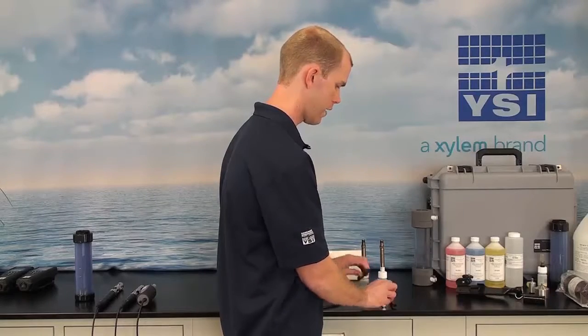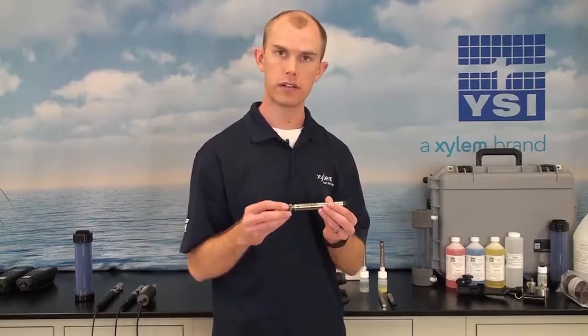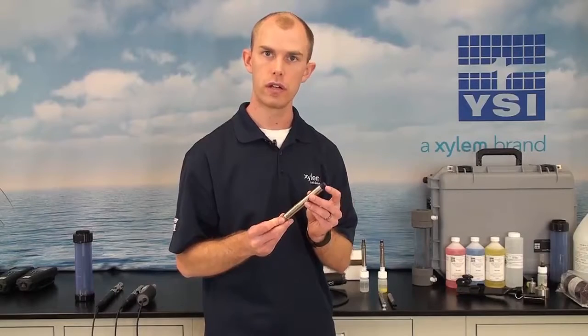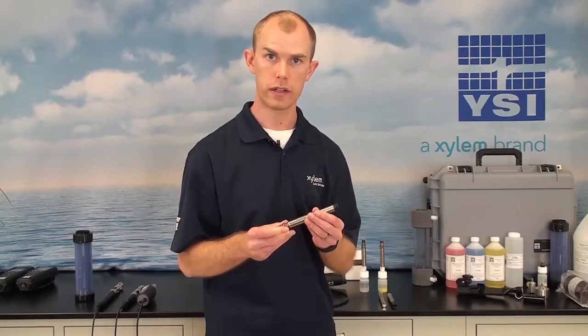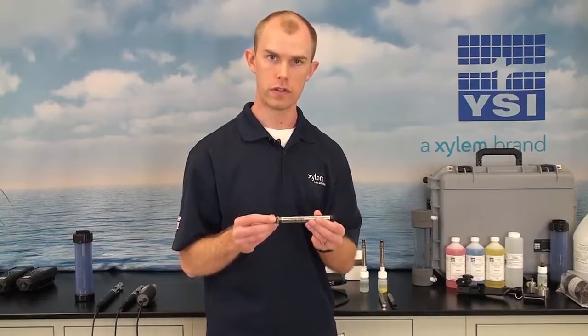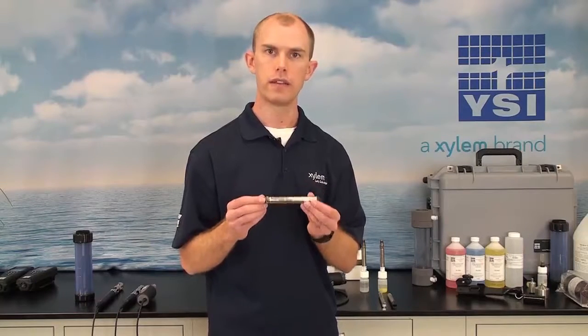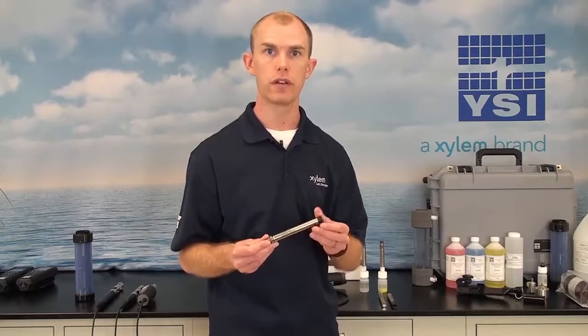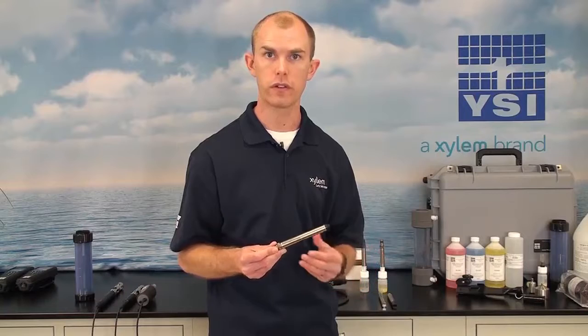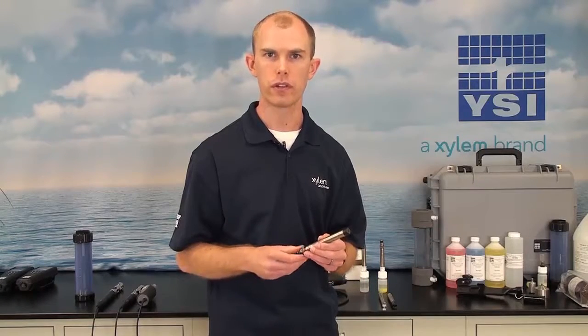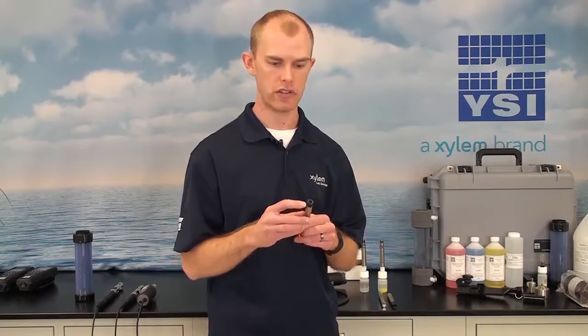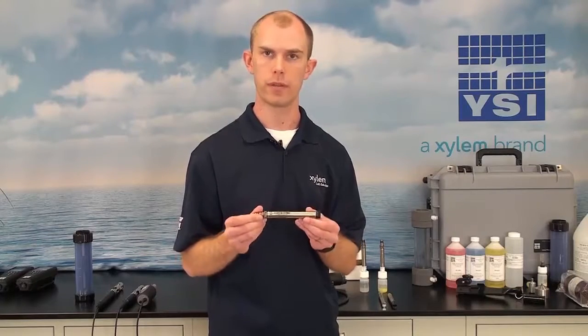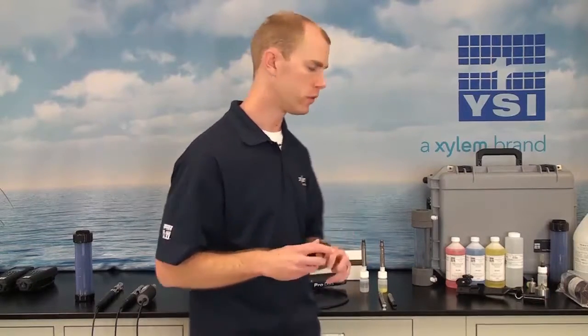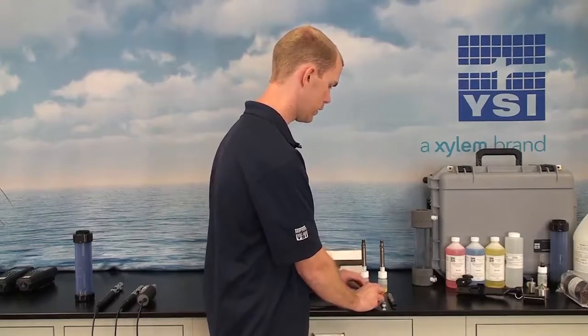We also have a dissolved oxygen sensor that features optical sensing technology. So this is another sensor that we have available. This does have lots of benefits over the conventional electrochemical sensors, where you have to stir your sensor. You have to change the membrane on the tip of the sensor a lot more often than you do with optical. So we do have the optical DO with the ProDSS.